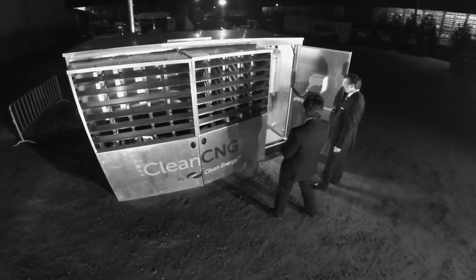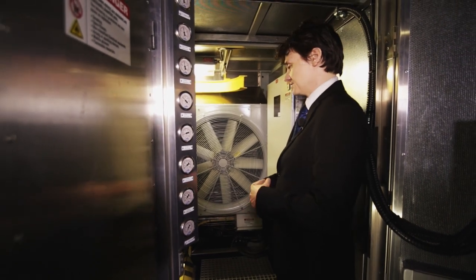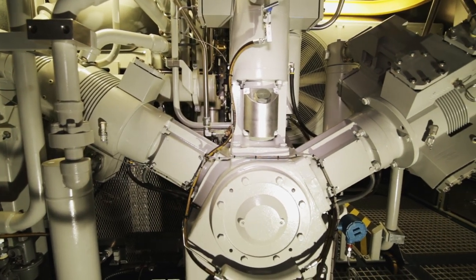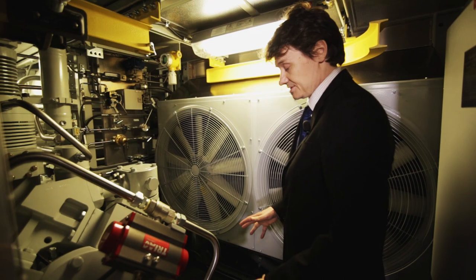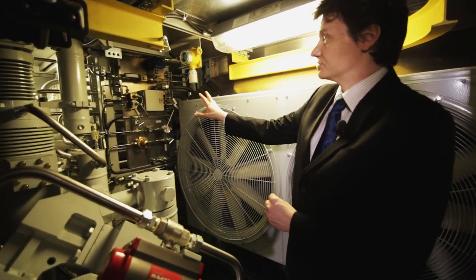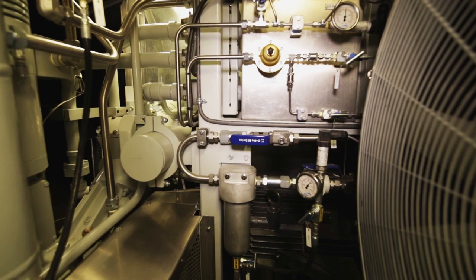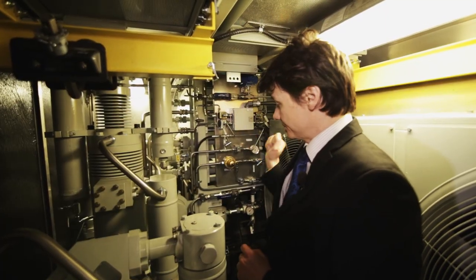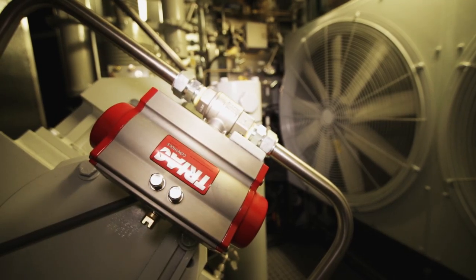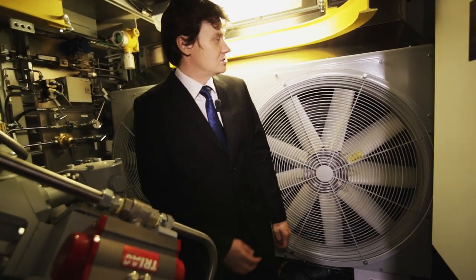In this design we created a service pathway which actually serves multiple functions. We located all the major serviceable items very close to this service pathway: the inlet filter, the discharge filter, the mechanical control opener with all the solenoids, the motor connections, the belt and the sheave. We have all the isolation valves in one place inside. We also have two fans with improved airflow and cowling, with very efficient heat exchangers behind.